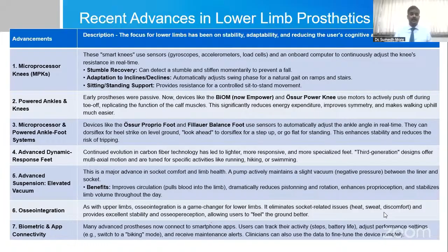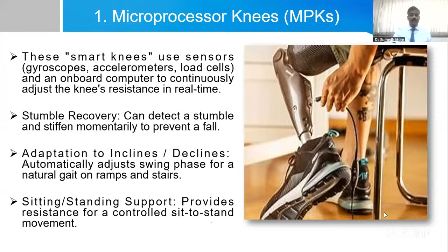Microprocessor knee: these smart knees use sensors, that is gyroscopes, accelerometers, load cells, and an onboard computer to continuously adjust the knee resistance in real time. Stumble recovery: it can detect a stumble and stiffen momentarily to prevent a fall. Adaptation to incline and decline: it automatically adjusts swing phase for a natural gait on ramps and stairs. Sitting and standing support provides resistance for a controlled sit to stand movement.